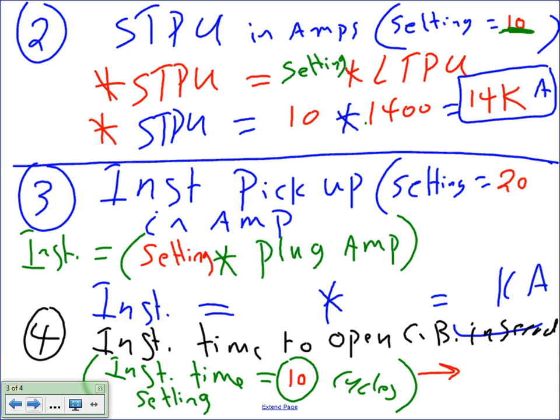Yep, absolutely. So the formula for this one is the instantaneous equals the setting multiplied by the plug amps. It's very important, guys, to know which amps. There are so many amps. The plug amps. In this case, what's the setting? 20. What's the plug amps? Anybody remember what the size of the plug was? 2000 is the plug, right? We started with the plug amps. And that will give me 40K. Done. No gimmicks, nothing to it.